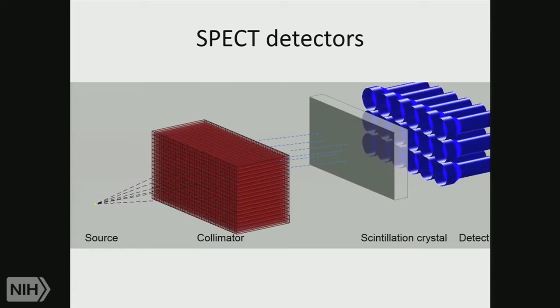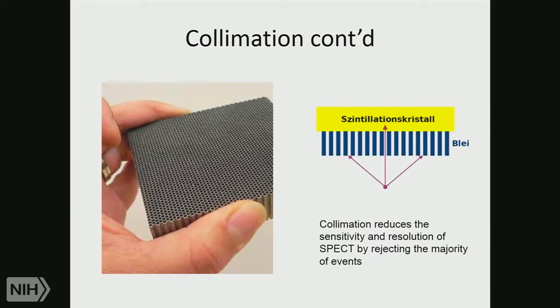And very similarly, you put a collimator here in front of the detector so that only the parallel gamma rays are absorbed. But that makes it inefficient. So this is a picture of just such a collimator, and you can see these very tiny holes, and it's fairly thick. So you can imagine that unless you're dead on here, you're not going to get through that collimator. And then this is depicted here. So this gamma ray will get through, but these gamma rays will be deflected by the collimator.